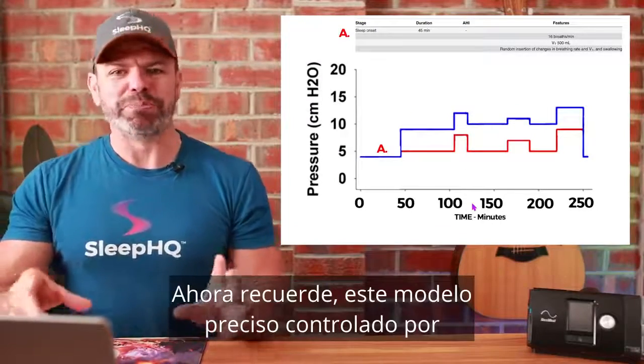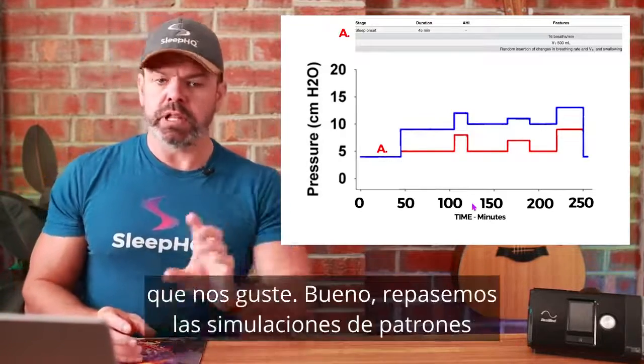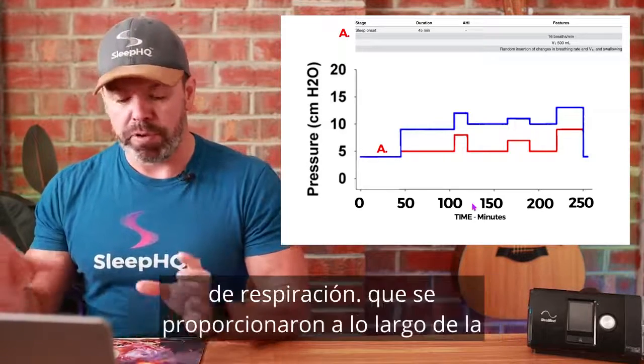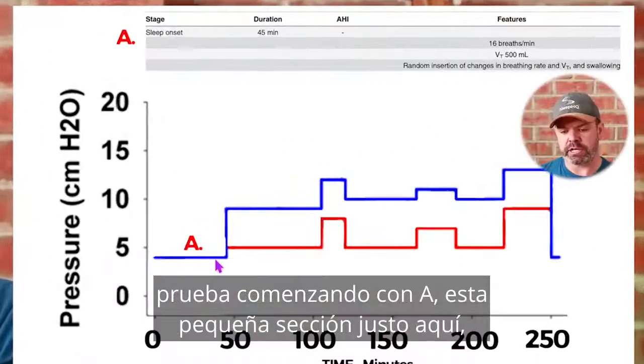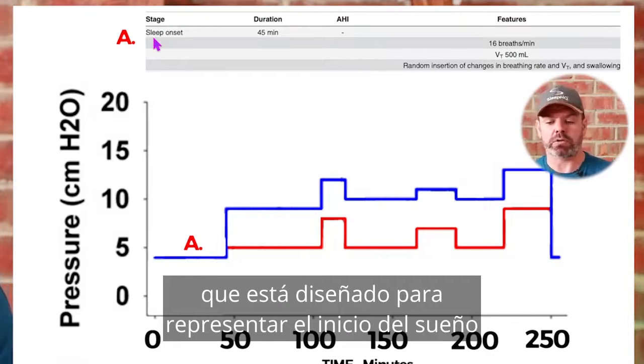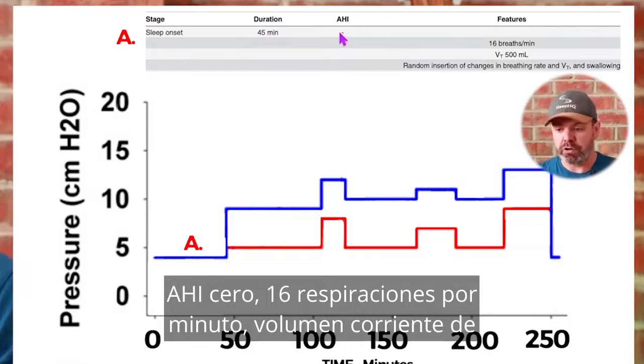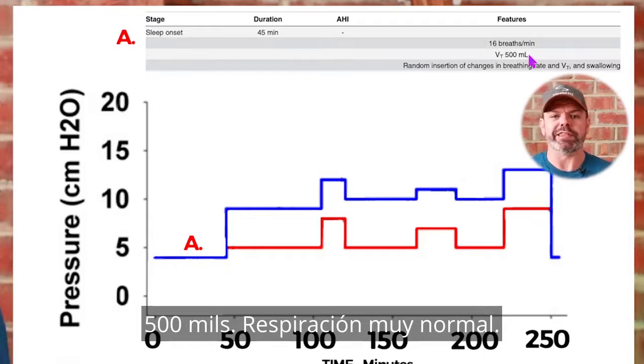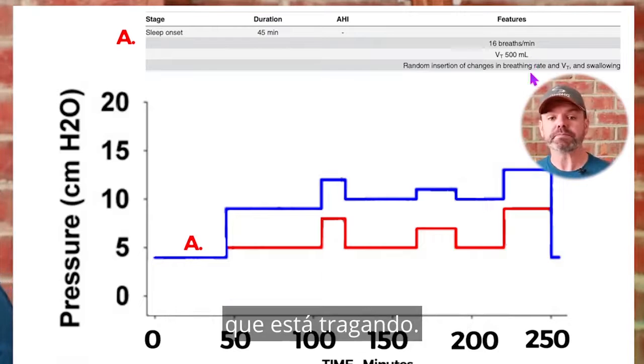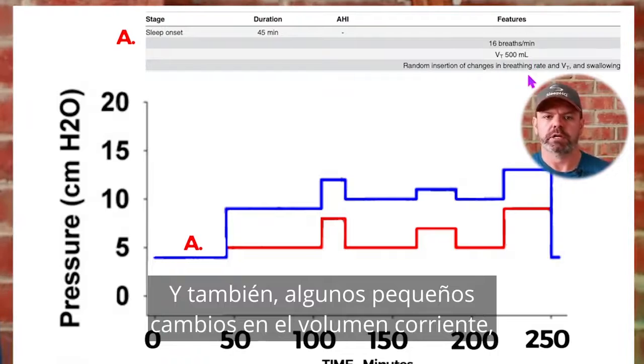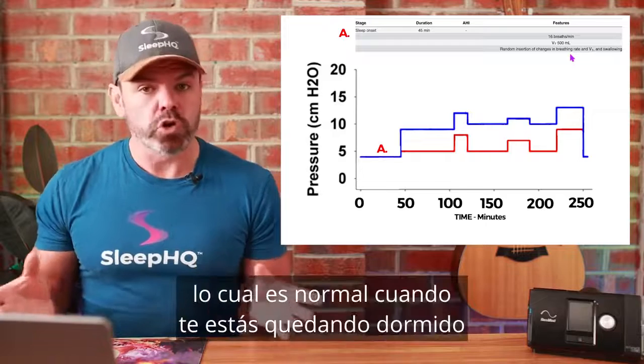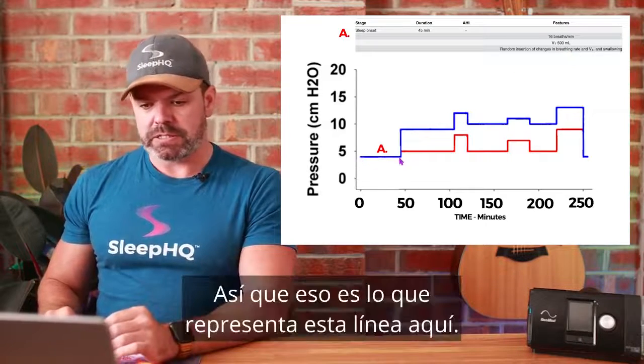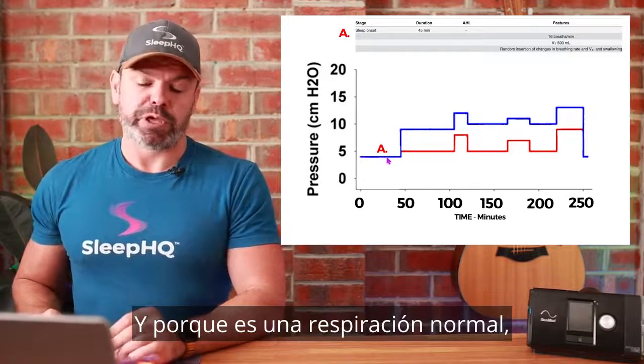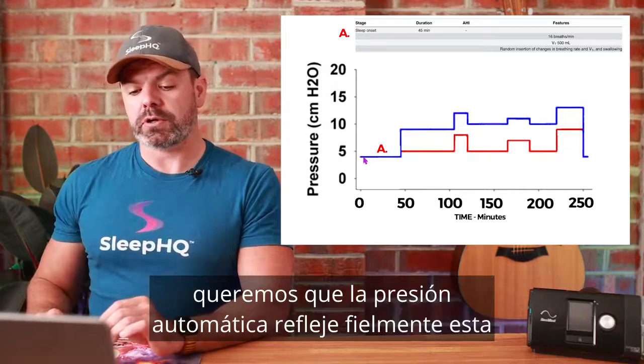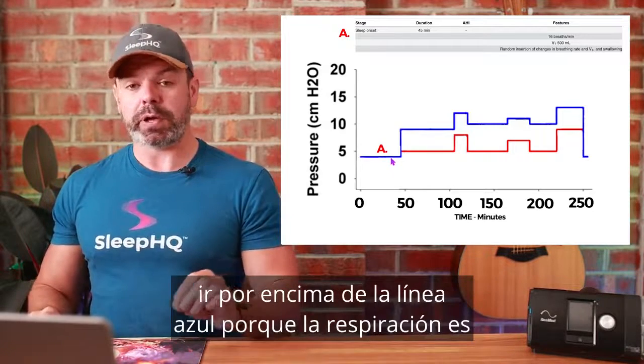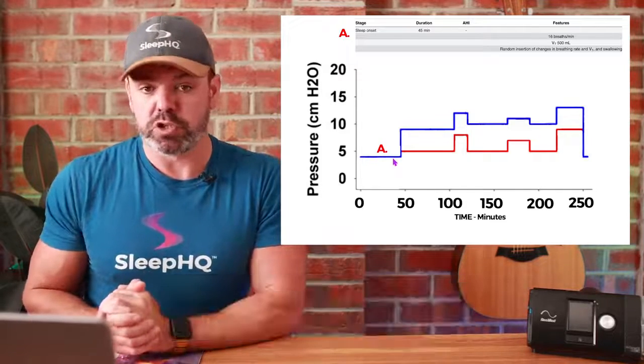Now remember, this precise computer-driven model can replicate any breathing pattern we like. Well, let's run through the breathing pattern simulations that were provided throughout the test, starting with A, this little section right here, which is designed to represent sleep onset, 45 minutes in duration, AHI 0, 16 breaths per minute, tidal volume of 500 mils, very normal breathing. They did throw in a few little booby traps here, which is swallowing, and also some small changes in the tidal volume, the amount of air flow into the lungs, which is normal when you're falling asleep at the beginning of the night. So that's what this line represents here. And because it is normal breathing, we want the automatic pressure to closely mirror this line. There really is no need for that automatic pressure to be going above the blue line because breathing is normal.